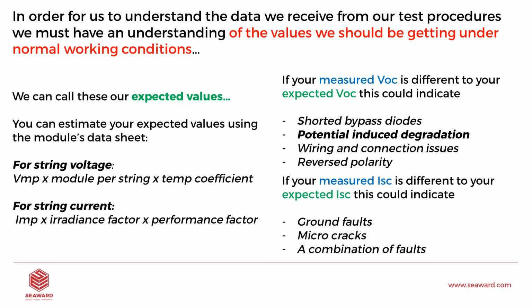And the good thing about the Solar Utility Pro is that if you do connect to a system, it will tell you if there's reverse polarity. And also, if there is a faulty bypass diode, you should see the voltage swinging dramatically from low to high, low to high. That's the bypass diode kicking on and off when it shouldn't be. Similarly, with ISC, we can tell a lot if we compare our measured to our expected, particularly with ground faults and micro cracks. So if we're operating at 500 watts per meter squared, the back of the panel will tell us, okay, at 1000 watts per meter squared, you should see, let's say, 8 amps. So then if we do some calculations, we can say, okay, at 500, I should see 4 amps. Now, if I see less than what I expect, then I know there's an issue with that string.